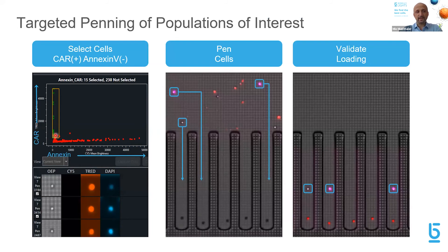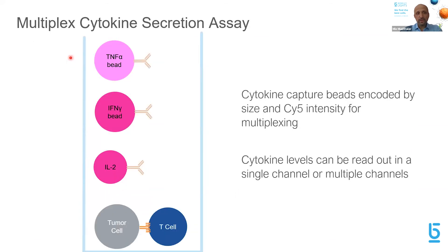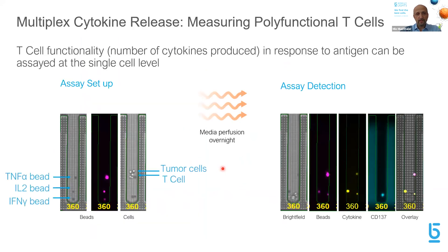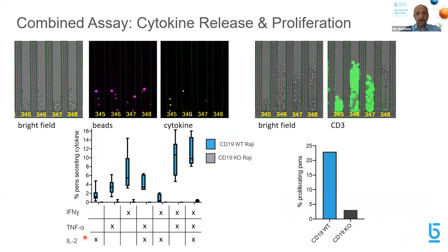The system can selectively enrich for CAR-T positive cells that are still living, excluding any cells stained by Annexin A5 as dead cells, enriching only living CAR-T positive cells. To increase multiplexing capability, different size beads with different autofluorescence are used; the software automatically differentiates between these beads to identify TNF alpha, interferon gamma, and interleukin-2, characterizing different cytokine secretion levels and intensities. In the experiment with three different beads, the software identifies and quantifies subpopulations of T cells secreting a single cytokine, any combination of two cytokines, or all three cytokines.